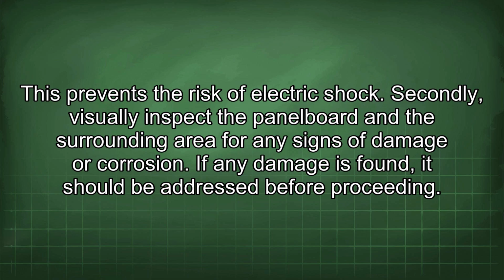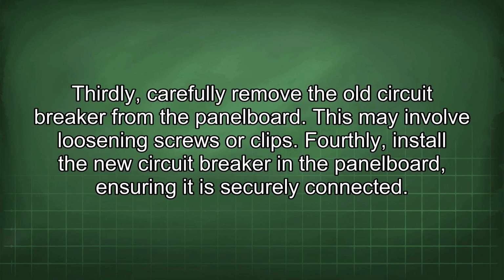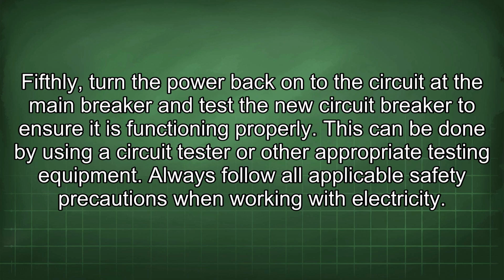Secondly, visually inspect the panel board and the surrounding area for any signs of damage or corrosion. If any damage is found, it should be addressed before proceeding. Thirdly, carefully remove the old circuit breaker from the panel board. This may involve loosening screws or clips. Fourthly, install the new circuit breaker in the panel board, ensuring it is securely connected. Fifthly, turn the power back on at the main breaker and test the new circuit breaker to ensure it is functioning properly. This can be done by using a circuit tester or other appropriate testing equipment.